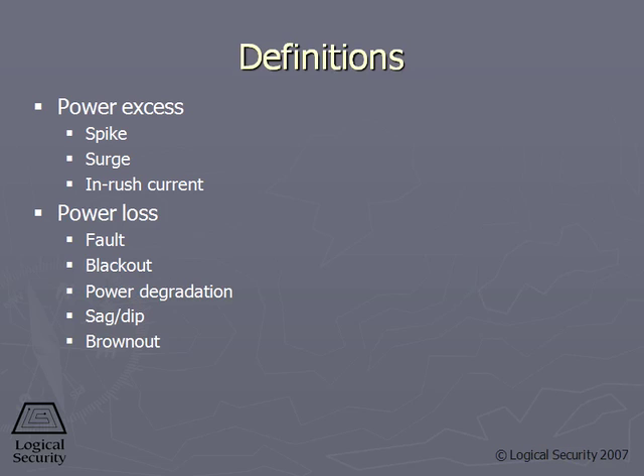Power degradation and power sag imply a low voltage situation for a brief period of time, and a brownout is a low voltage situation for an extended period of time. Some things we can do to help make our electrical power more stable and steady. First, don't just pull the plug on devices. Go through a clean and orderly shutdown of those devices.